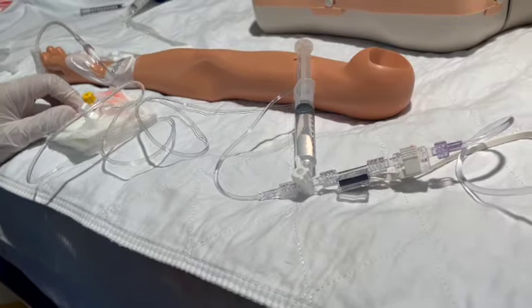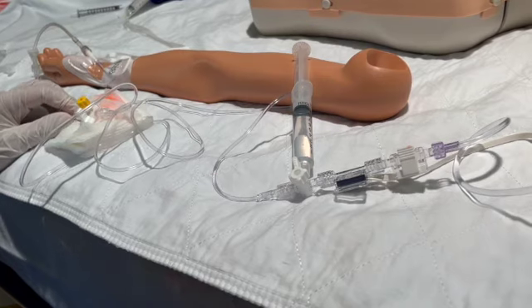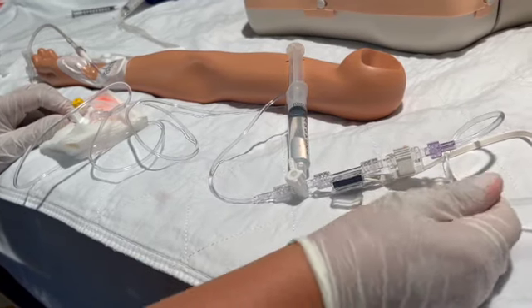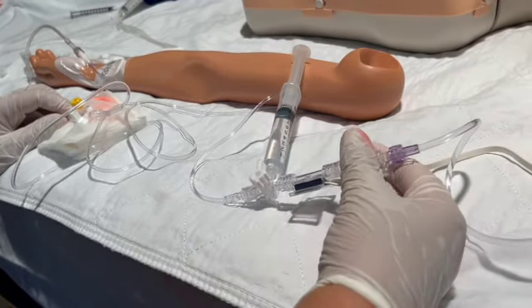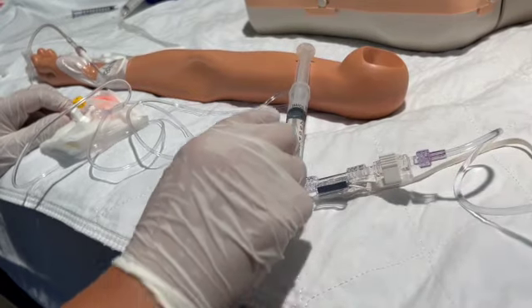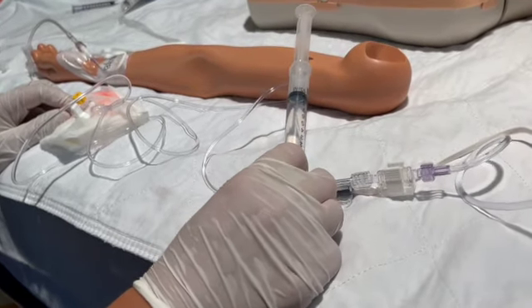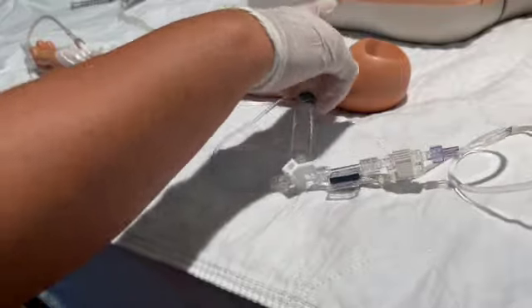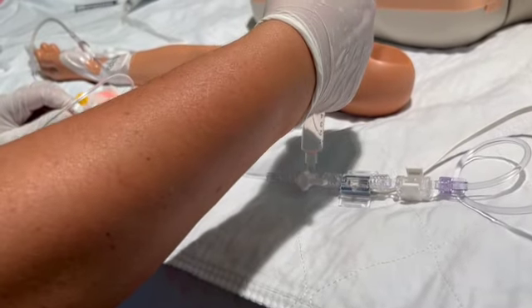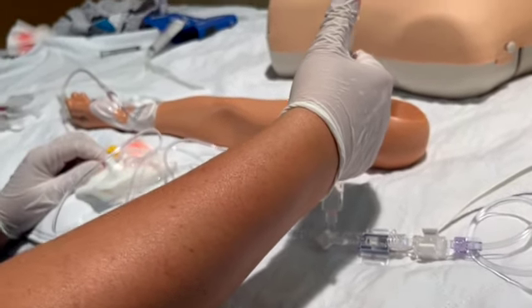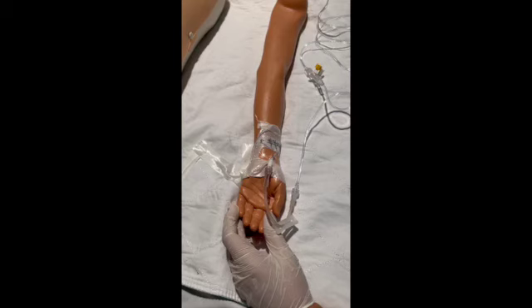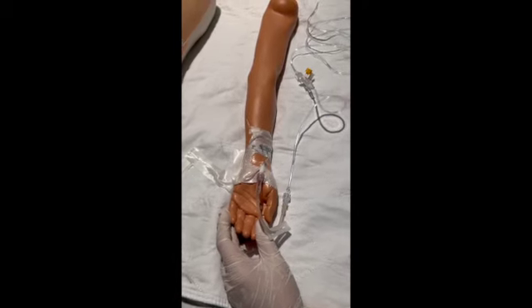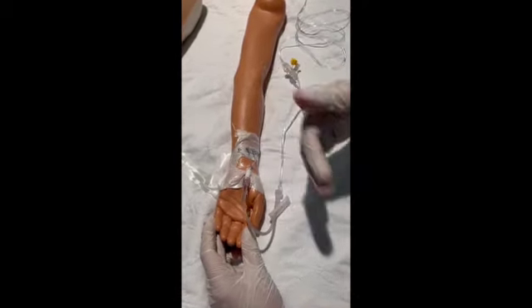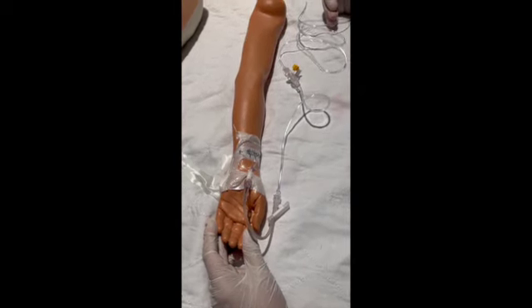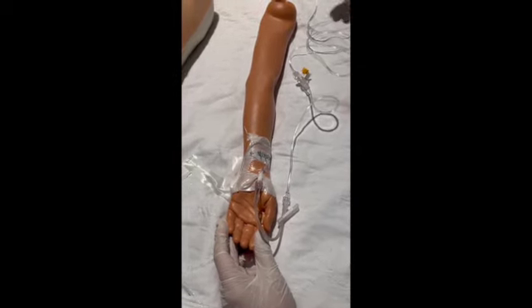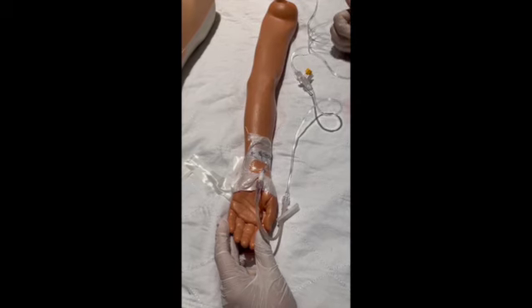All right. And then you're going to turn the stopcock back up toward your sampling port and replace your cap. If you're concerned at all about fluid restrictions in your patient, another way to clear your line, instead of using the buttons to just flush through your lines, is to use the syringe. You can turn it off toward the transducer and clear your line with your 10 cc syringe so that you are giving the patient a little less volume. Another important thing to remember is to try to keep the arm in a somewhat neutral position if the patient tolerates it so that you can ensure an accurate wave on the monitor.